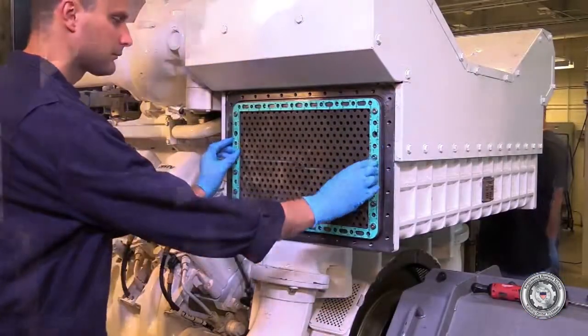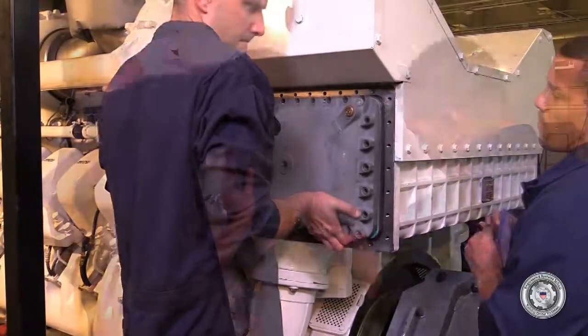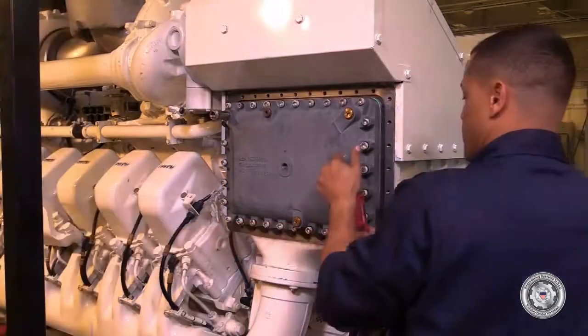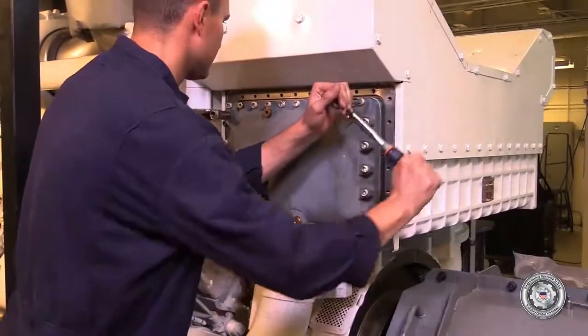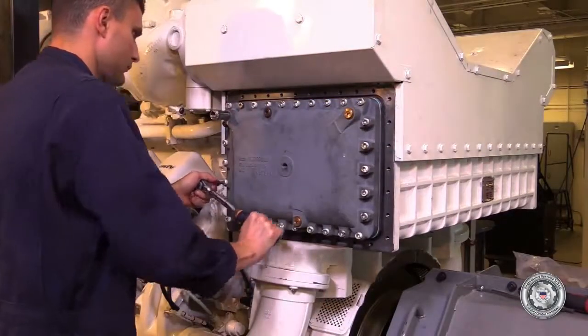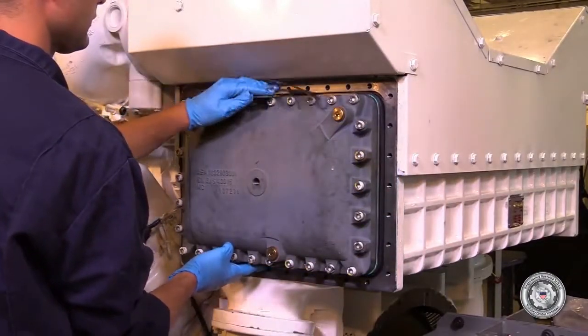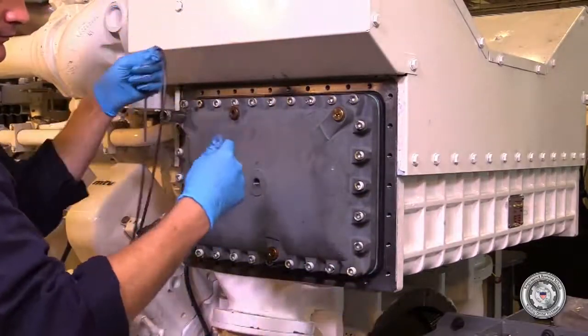Install the port side gasket and inner cover and attach with the Allen bolts. Tighten to specified torque. Install the guide band and the sealing cord. The guide band comes pre-cut — that is normal. Ensure the sealing cord is properly in place.